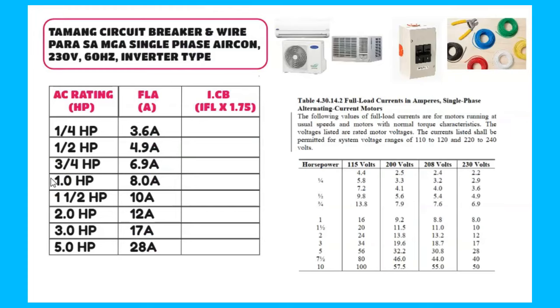And then from the table, meron na tayong nakuhang load amperes. Okay, so 1/4, meron tayong 3.6. Sa 1/2, meron tayong 4.9. Sa 3/4 HP, meron tayong 6.9. Sa 1 HP, meron 8. Okay. Until sa 5 HP, meron tayong 28 ampere. So, meron tayong babasahin code related to size up the circuit breaker.